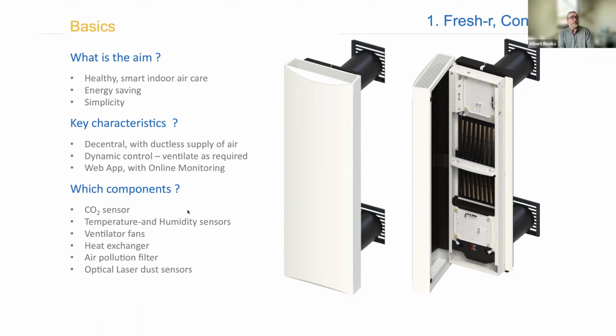So key characteristics is decentralized and demand control. And so demand control is driven by the fact that we're that little line that says which components. It says it's got a CO2 sensor on board. So on the intake coming back from wherever it's mounted, it's always looking at how much CO2 is in the air. And as CO2 rises, it increases the fan rate. As CO2 falls, it decreases the fan rate, which is really smart, because we've always got a loss.